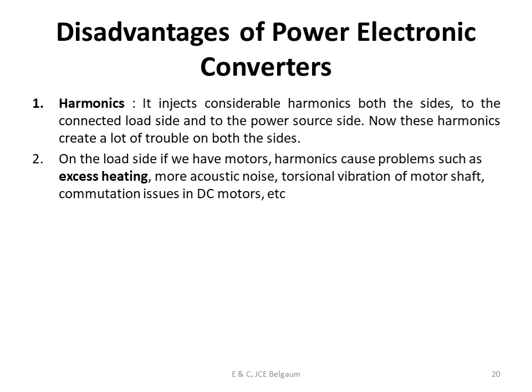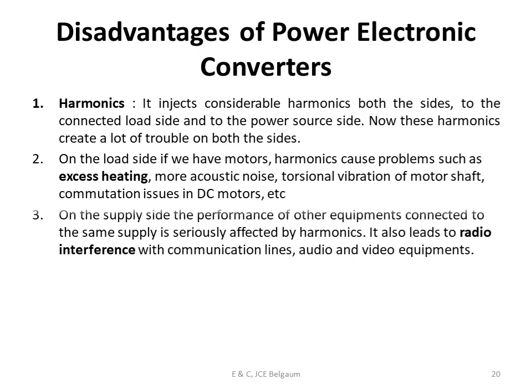Next is excessive heating. We are normally going to connect motors at the load, and these harmonics are going to cause heating at the motor, more noise, more torsional vibrations of the motor shaft, commutation issues in DC motors, etc. So this is the way the load will be affected by harmonics. And on the supply side, the performance of other equipments connected to the same supply is seriously affected by harmonics. It also leads to radio interference with communication lines, audio and video equipments.